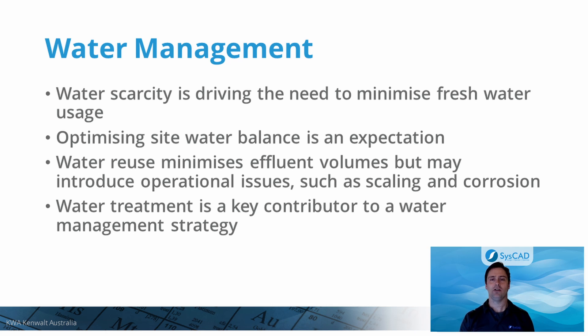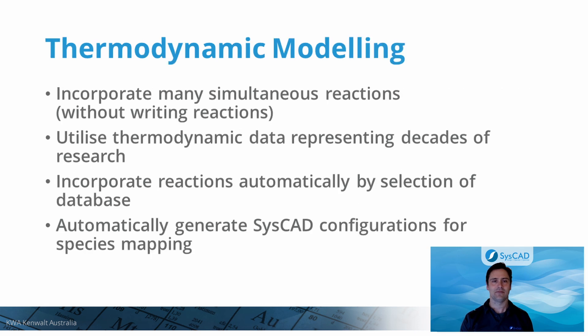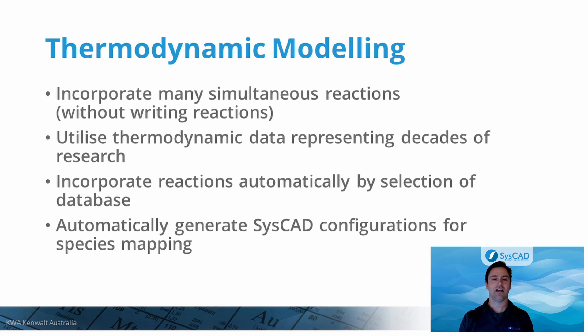Optimizing the water balance to minimize water use is not only a public expectation, but is also important for managing water treatment plant loading. However, water reuse can introduce significant operational challenges, such as mineral scaling and corrosion. SysCAD with TCE can predict mineral scaling propensity and regions of aggressive chemistries where corrosion is likely. Using SysCAD with the TCE add-on, all relevant reactions are incorporated into simulation of a reaction vessel through the selection of a database. This approach leverages libraries of thermodynamic data representing decades of research. An automated mapping approach is employed, where each SysCAD component is matched to an equivalent TCE component, allowing seamless use of these highly complex calculations as needed, with simplified calculations used elsewhere.